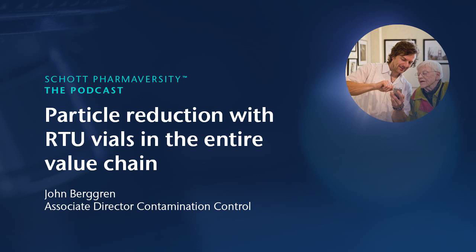So as a sealing material, the industry leader for drug and medical devices is DuPont Tyvek. Tyvek is a strong, breathable polyethylene material. It has a fantastic microbial barrier. They have a very low risk of shedding, as long as you don't mess with it, as long as you don't stretch it, as long as you don't cut it.